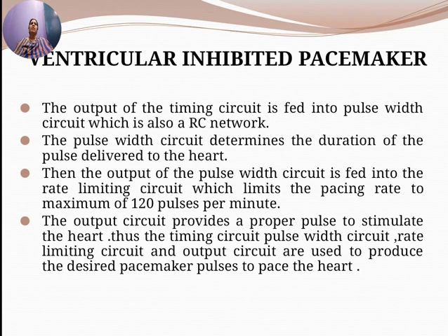The reversion circuit allows the amplifier to detect the R wave in low level signal to noise ratio. In the absence of the R wave, it allows the oscillator in the timing circuit to deliver pulses at its preset rate. The timing circuit consists of an RC network, a reference voltage source and a comparator which determines the basic pulse rate of the pulse generator.